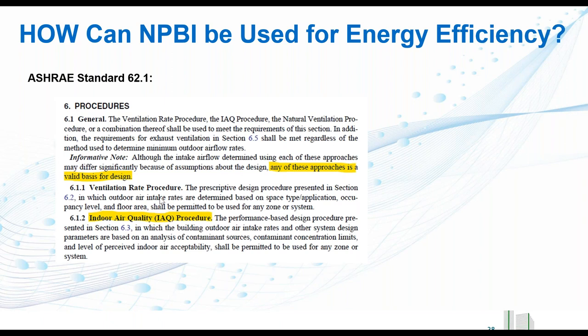What's starting to pick up in momentum and popularity is the indoor air quality procedure. This is performance-based, and it has to take a look at and analyze contaminant sources, concentration limits, how many people are in the space, what their level of activity is. And from all of that, it can potentially offer a lower outside air requirement. The key is we have to control the indoor contaminants, and then we can reduce how much outside air we can introduce into the building. To do this, there is a calculated approach, and it is very specifically spelled out in the ASHRAE standard how that is done, and that is the process that is used.